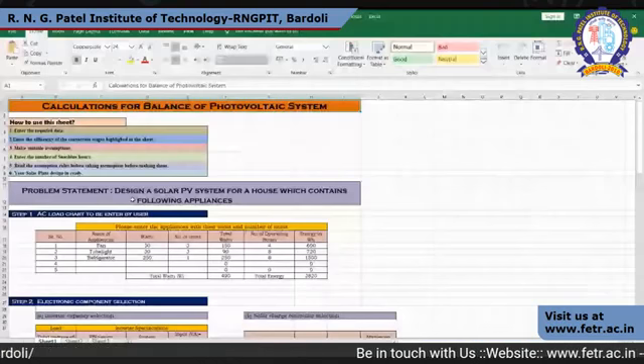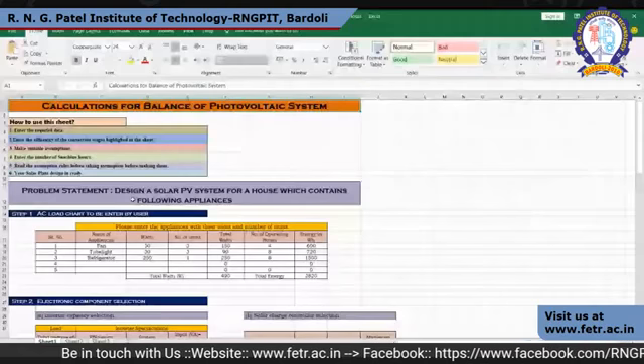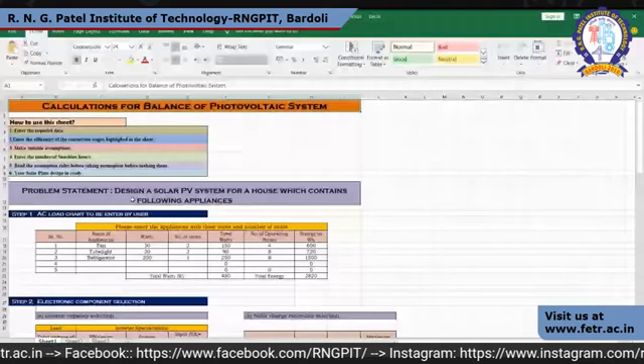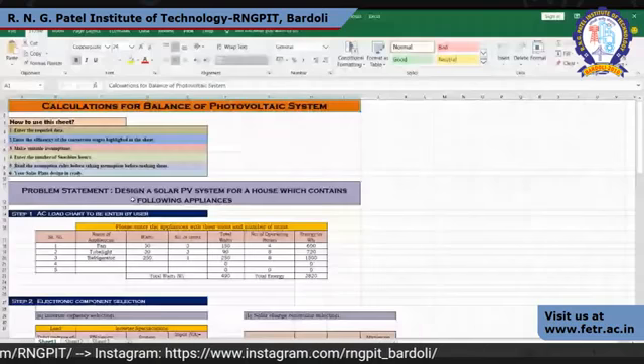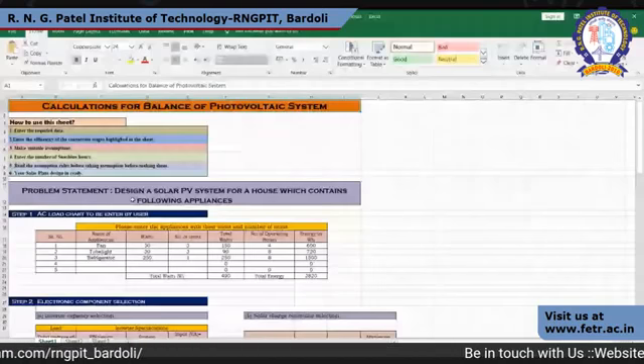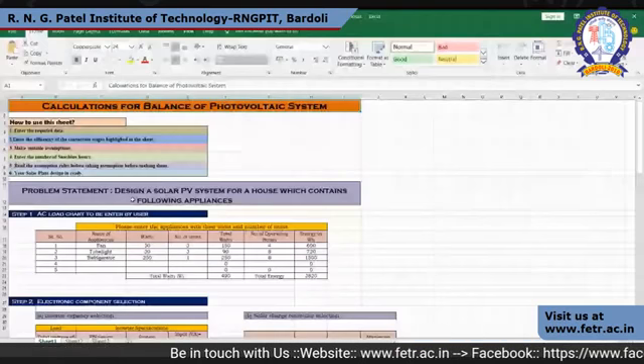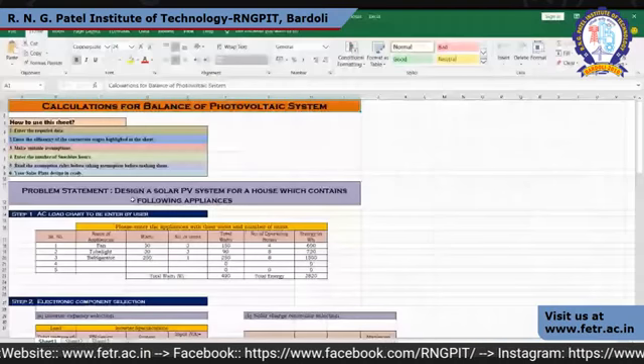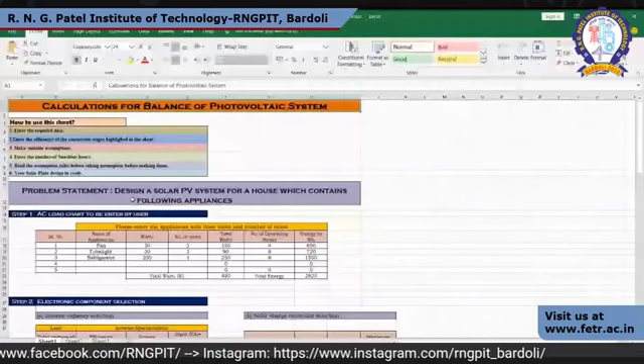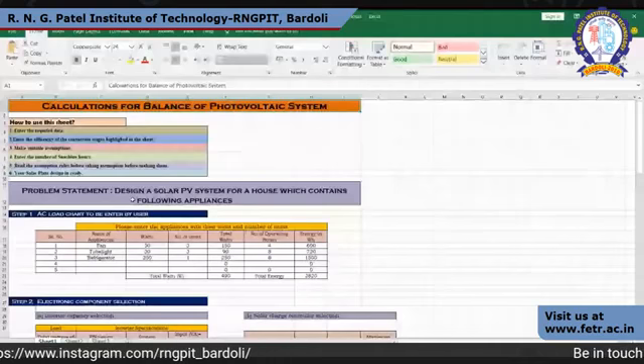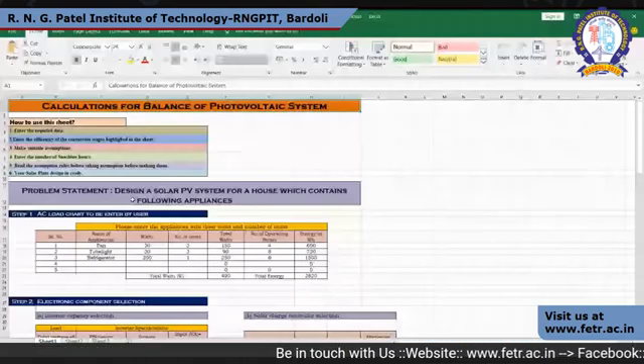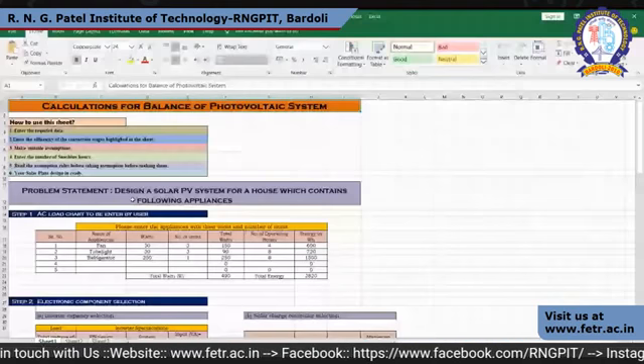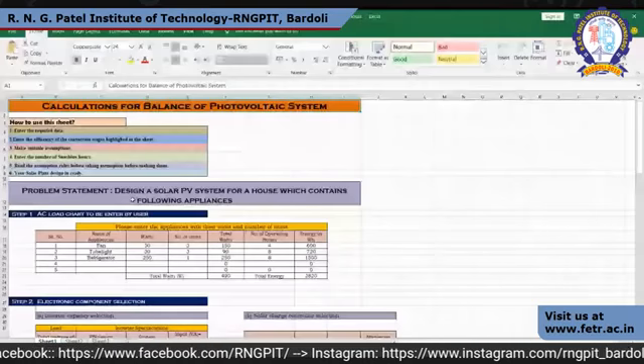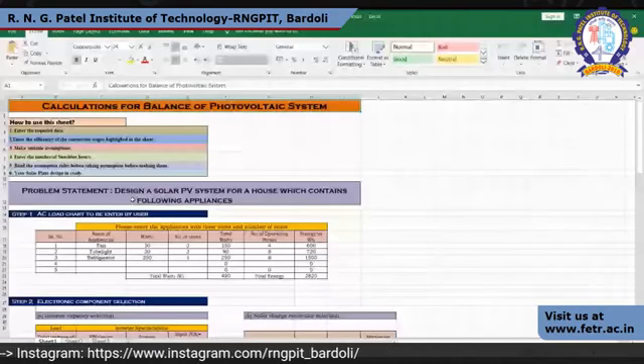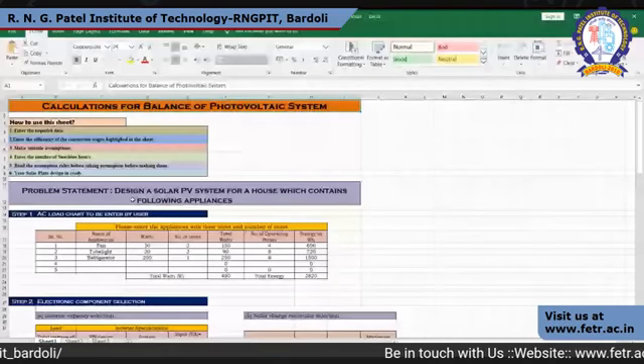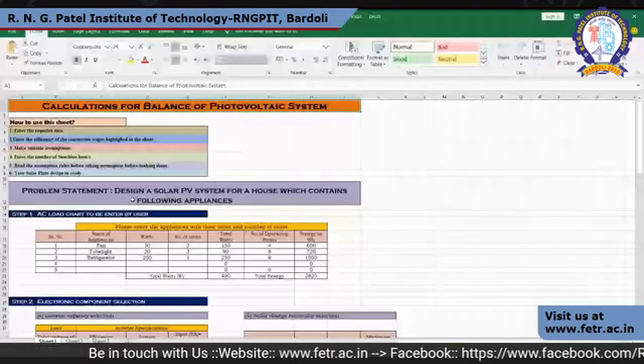This total wattage is AC wattage. Particularly for the inverter, this wattage we are calculating is the AC voltage. But power equals voltage into current. In the DC system at our home, we can have a DC load or an AC load, more or less at unity power factor. So we will assume 96% efficiency of the inverter. We are having the KVA capacity as per the load requirement. Similarly, we can do it for the energy calculation. Mind well, for good design, ultimately we will go for the same efficiency in the case of energy as well as the power output.